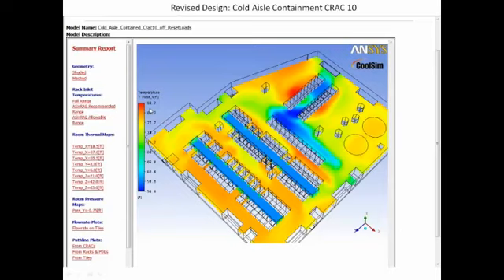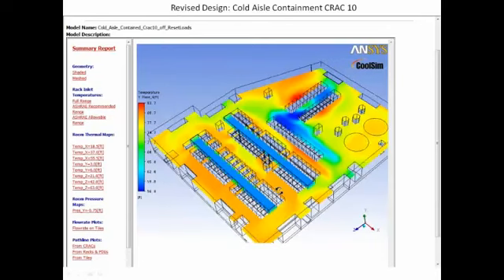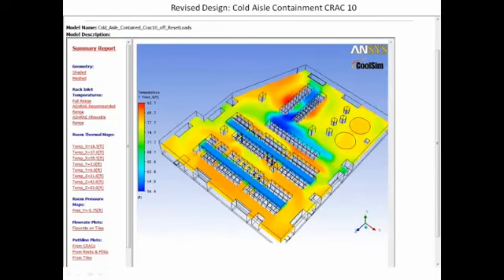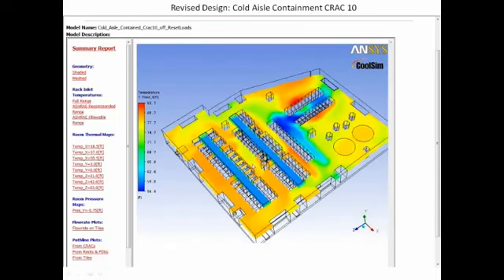In other words, the human factor prevails: people get nervous in the data center when it's hot, so they just naturally want to turn that thing down. And that does have an effect. So I call it the human factor. It's not a science issue. It's not a thermodynamic issue. It's human factors, therefore cold aisle containment. I tend to prefer hot aisle containment whenever I can get it for that reason.